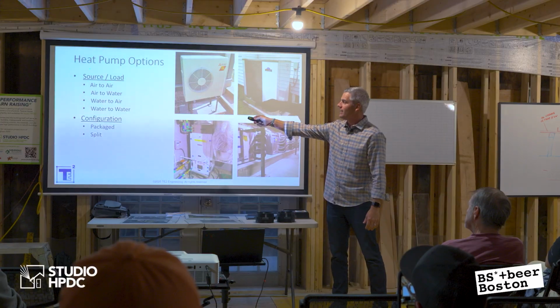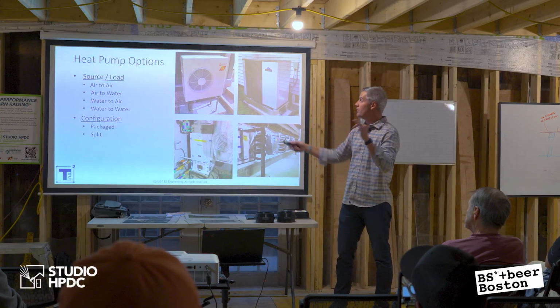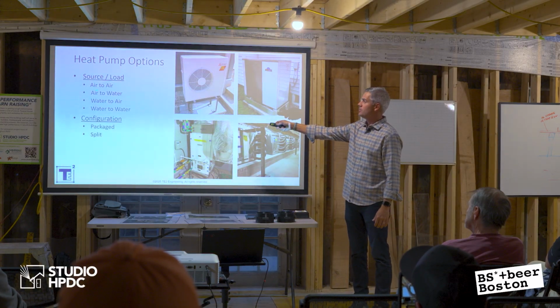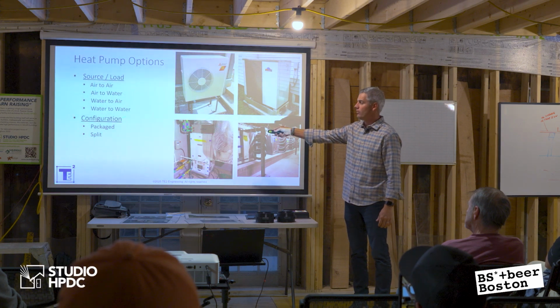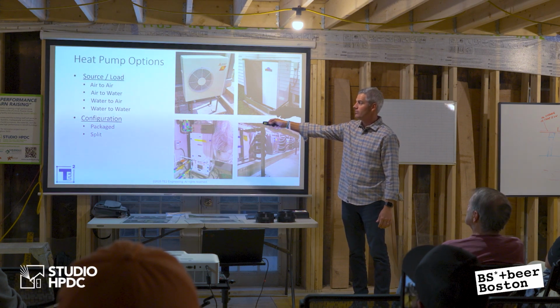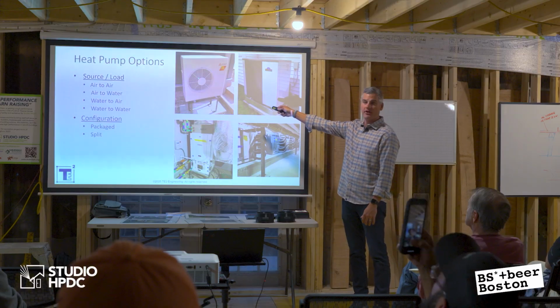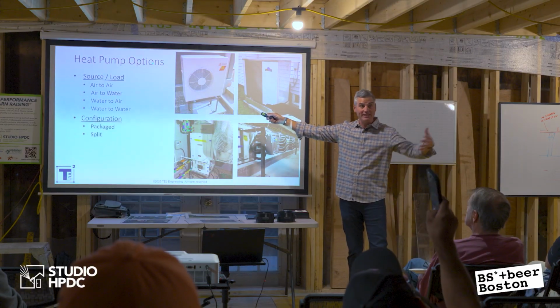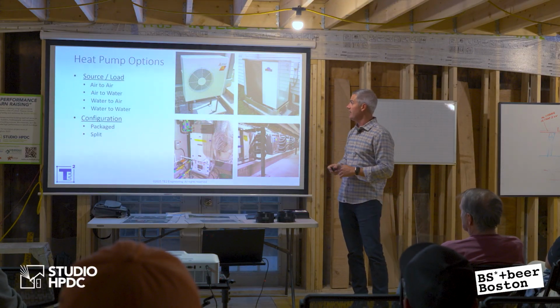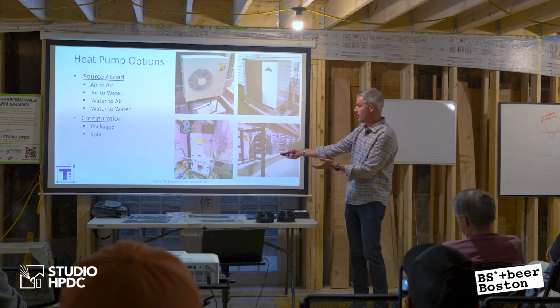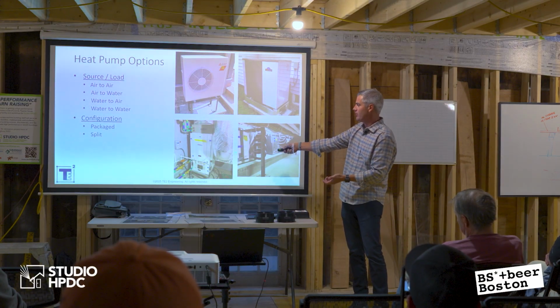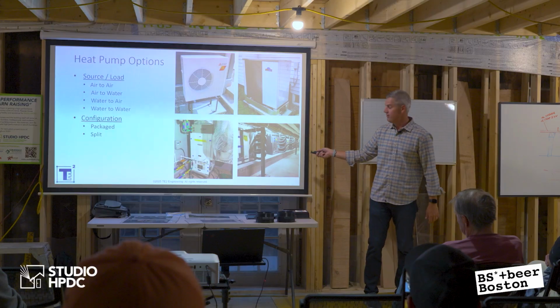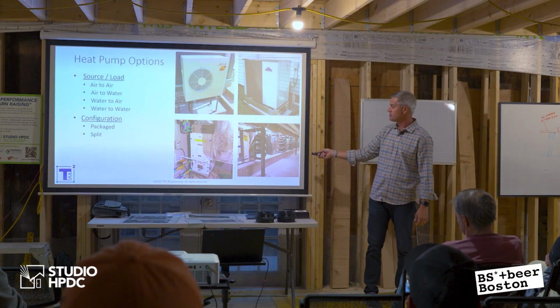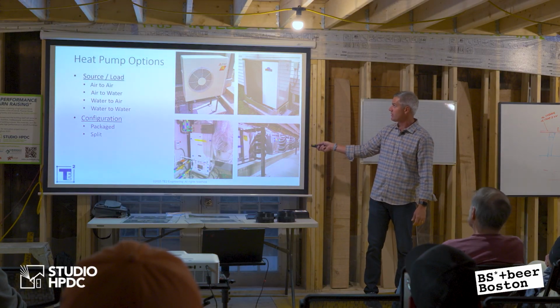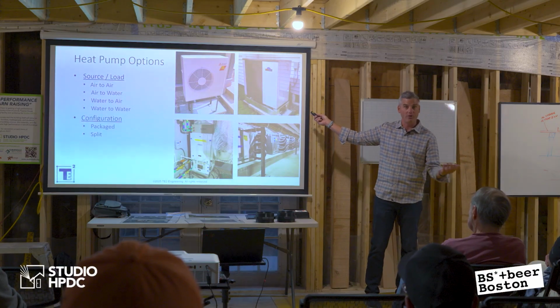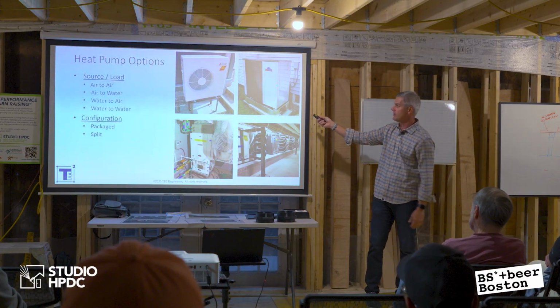They are all measured by source and load. You have air-to-air heat pumps. You have air-to-water heat pumps. You have water-to-air, water-to-water, right? So these ones would be geothermal based. This is an air-to-air heat pump. Everyone calls it a mini split. And then there's also geothermal, water-to-air. To put water pipes in, I get air blowing out in the ductwork. Here's water-to-water. Water goes in, water comes out. This is the geo loop going in. This is the heated and cooled water coming out. Here's an air-to-water heat pump. Air goes in, hot water or cold water comes out.